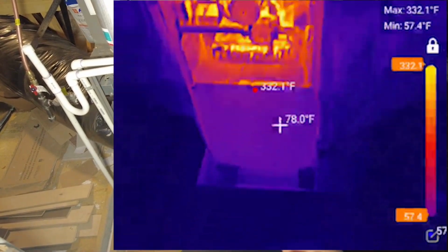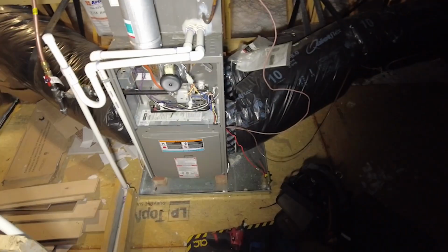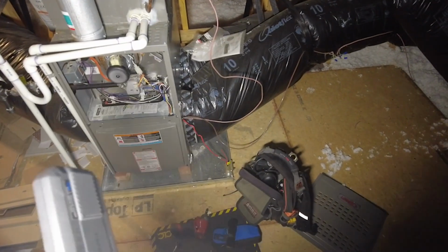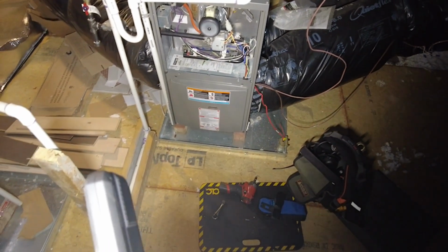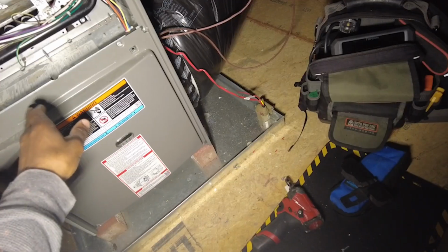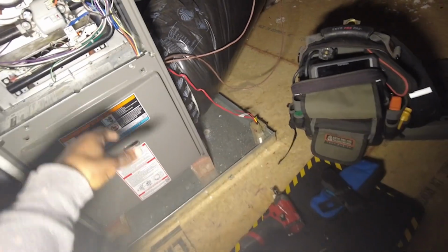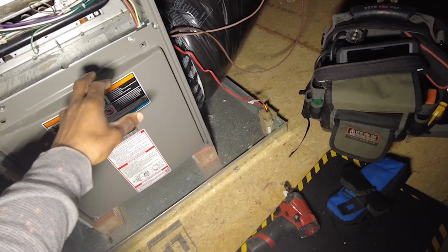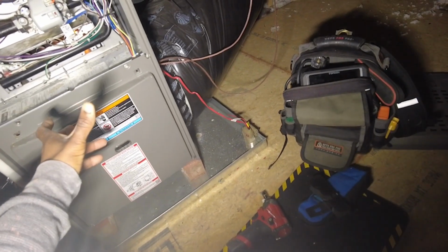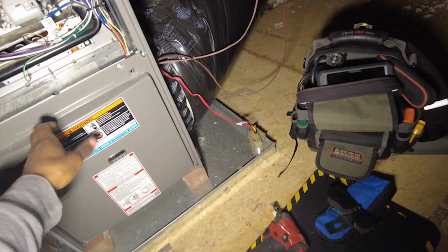So that right there completes, and we could have done that before we turned the system off, so that's one more thing you could have done with that, with the system running. All right, that's it. That's beautiful. The reason I cut the gas off before I open this up is you always want to make sure that heat exchanger has ample enough time to cool before you open this door and shut the power completely.